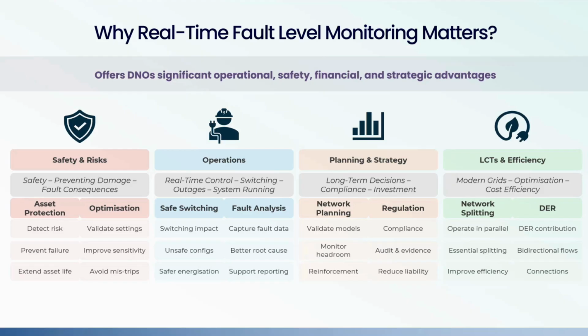So starting at the first pillar or dimension, this is basically the foundation. Everything else is built on this. So at the most fundamental level, this is all about safety and risk management. All our assets, whether it's switchgear, cables, transformers, and busbars, have hard fault level limits. And when these limits are exceeded, the consequences are immediate. So what the real-time fault level monitoring gives us is the ability to see risks developing early before something fails. That means preventing catastrophic damage and operating the assets within the design limits, as well as not operating blind. It helps us keep the protection settings of the relays appropriate as the network changes, and reducing mistrips and unnecessary outages.